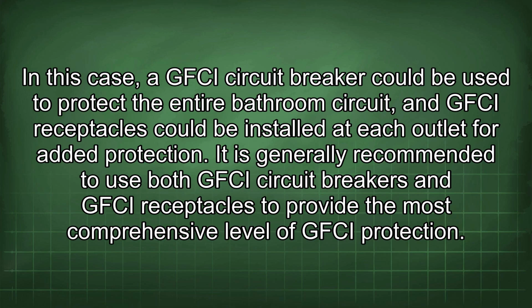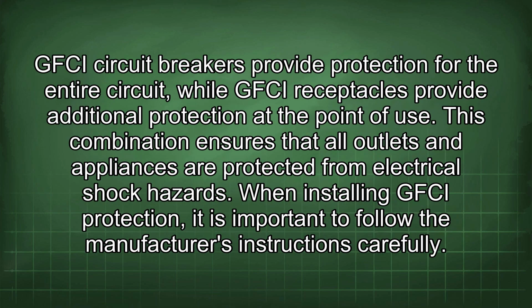It is generally recommended to use both GFCI circuit breakers and GFCI receptacles to provide the most comprehensive level of GFCI protection. GFCI circuit breakers provide protection for the entire circuit, while GFCI receptacles provide additional protection at the point of use. This combination ensures that all outlets and appliances are protected from electrical shock hazards.